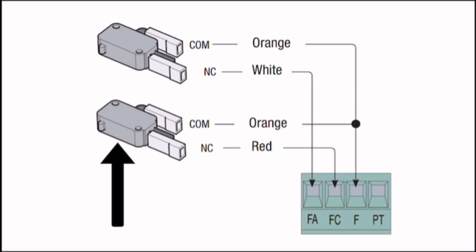Lower Limit Switch Closed Position: The COM (orange wire) connects to the F terminal on the control board. The NC (red wire) connects to the F.C. terminal, representing the fully closed position.